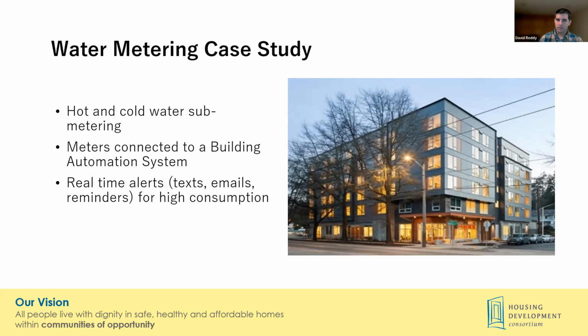So they still included hot and cold water submetering. That's their standard at DSC, and a standard for a lot of developers now. But in this case, the meters were connected to the building automation system to get more granular data, like every minute we could get reported data. It was also possible to alert facility managers if there was high consumption in real time, as soon as it happened, rather than a lot of metering systems that only let you know the next day if there was a lot of water use in an apartment. That was important because they had some issues with flooding, and there was also interest in understanding when water is being used, how much, and what we can do about it.